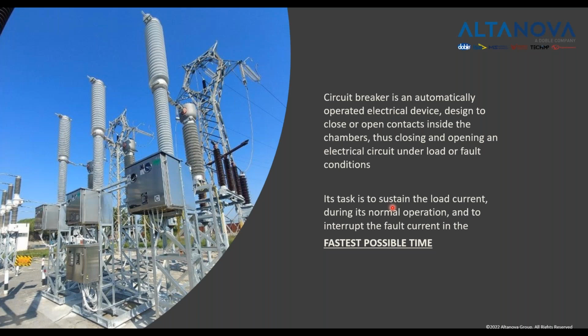The circuit breaker is an automatically operated electrical device, and it is designed to close and open contacts inside chambers. This operation must be done in the fastest possible time, because we have to clear the fault in the shortest time possible.